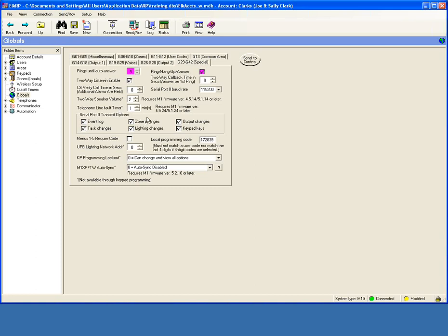If you maybe have an area where the phone service goes out for just a few seconds at a time here and there, you don't want to be alerted of that or have that logged or cause the keypad to beep and annoy your customer, that sort of thing. You can set this in minutes, as to how many minutes the phone line has to be down before the panel will do anything about it. So that's something we had a lot of requests for, and we managed to add that into the software here and into the firmware of the control.